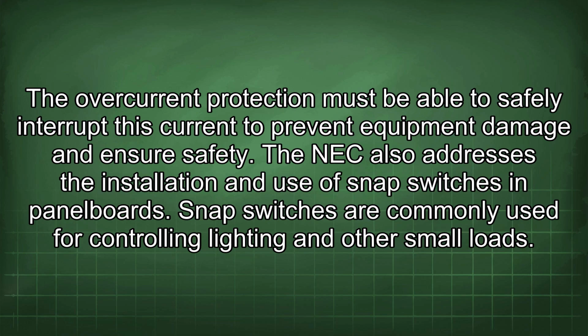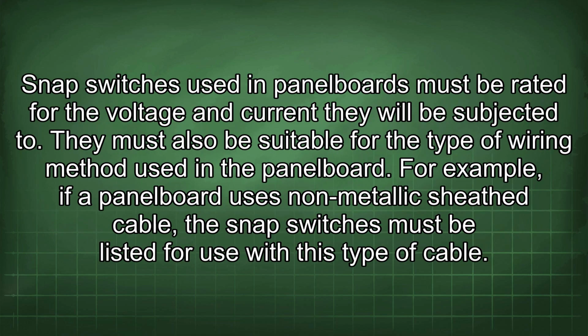The NEC also addresses the installation and use of snap switches in panel boards. Snap switches are commonly used for controlling lighting and other small loads. Snap switches used in panel boards must be rated for the voltage and current they will be subjected to. They must also be suitable for the type of wiring method used in the panel board. For example, if a panel board uses non-metallic sheathed cable, the snap switches must be listed for use with this type of cable.